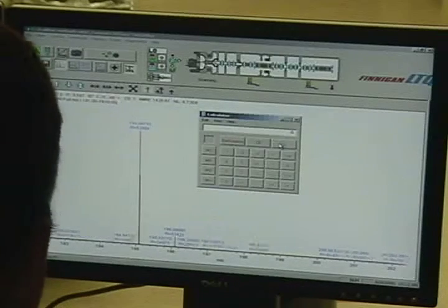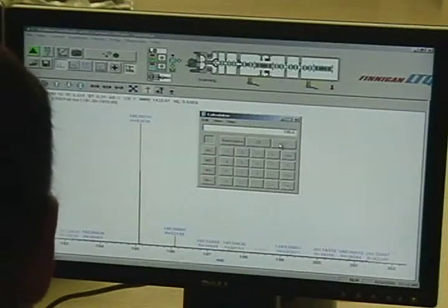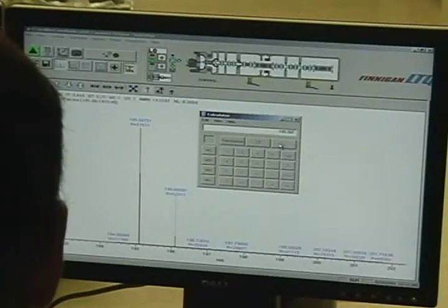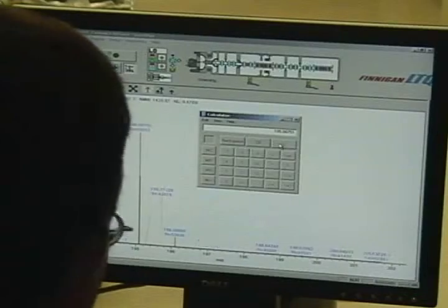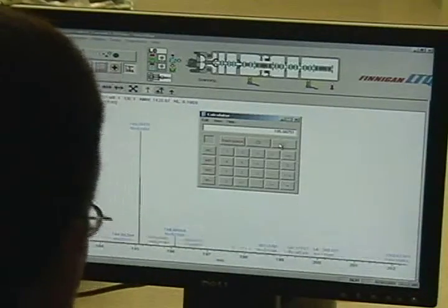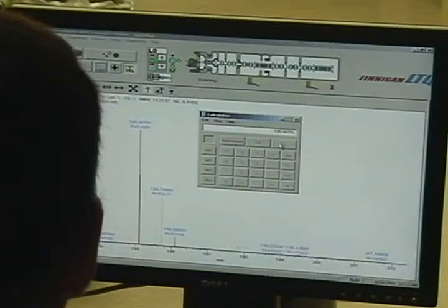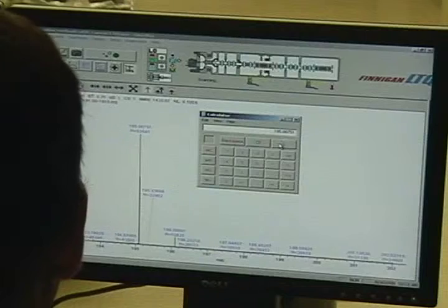But even up to 3E6, it's supposed to get sub 2 ppm, isn't it? Oh, no, nope. Is that not the case? No, that is not the case. So that's like 20 ppm up there? The problem is, instrument to instrument, that AGC is kind of a questionable number. So we always say 5E5 sub ppm is when the instrument's working properly.